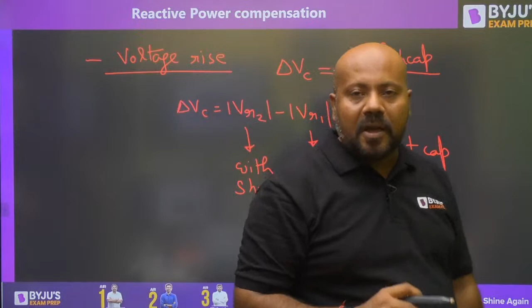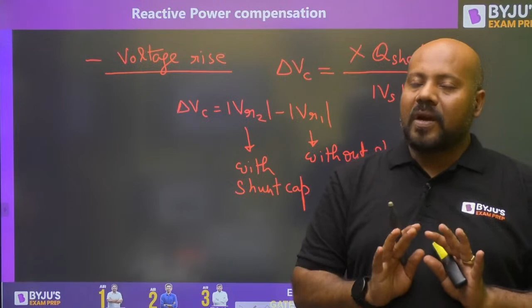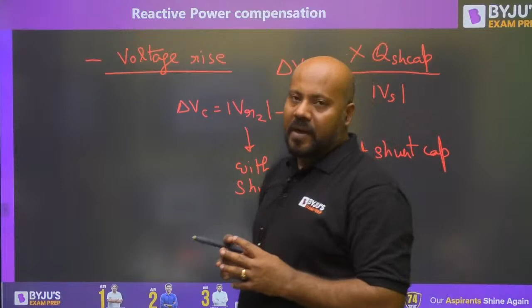And let me tell you, even if you get some voltage rise by applying the shunt capacitor, the shunt capacitor is generally not used for improving the voltage profile. Shunt capacitor is used to improve the power factor of the system, not the load, because once you design the load, the power factor of the load is fixed. You can't change it. You can just improve the system's power factor.